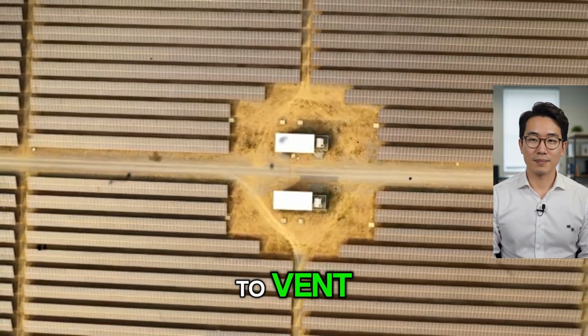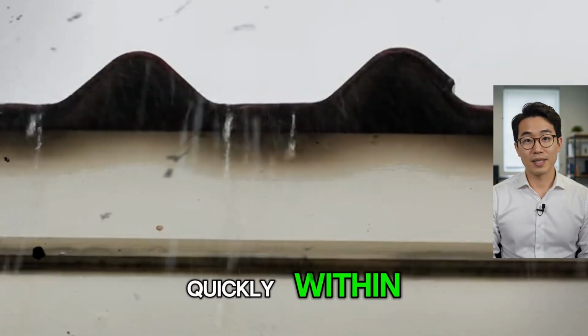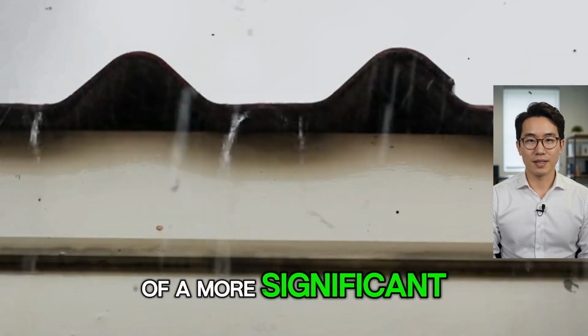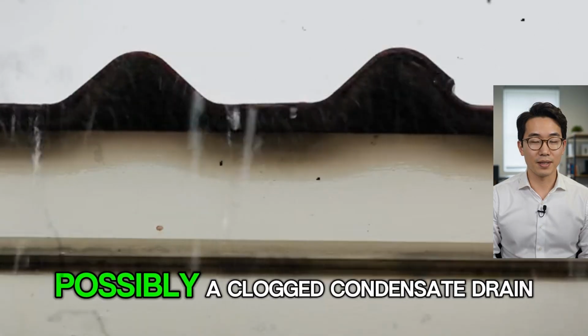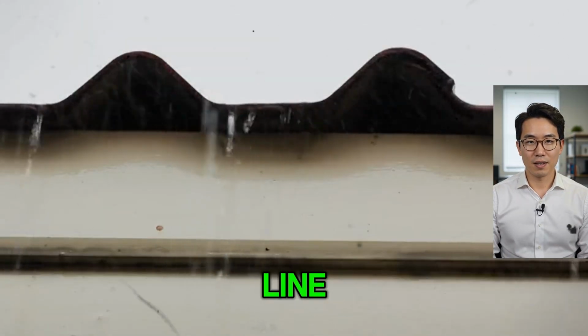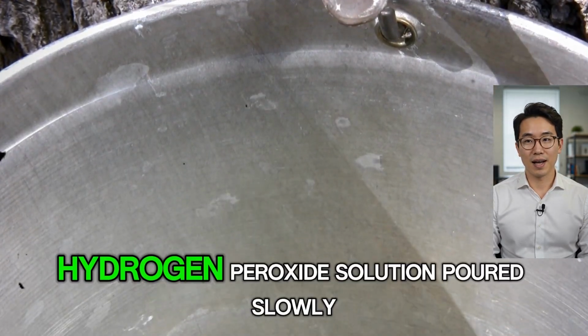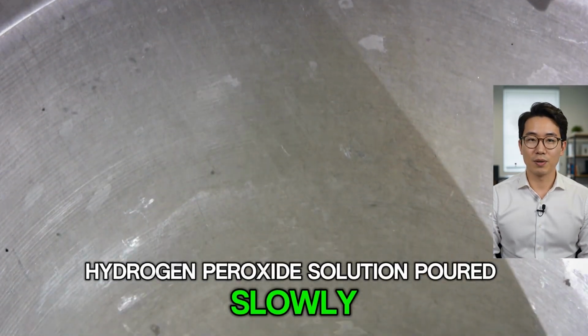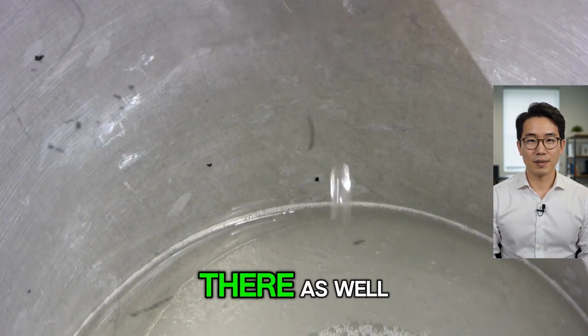And if the smell returns quickly, within a few weeks, that is a sign of a more significant moisture problem inside your system, possibly a clogged condensate drain line. In that case, you can use the same diluted hydrogen peroxide solution poured slowly into the condensate drain pan to clear buildup there as well.